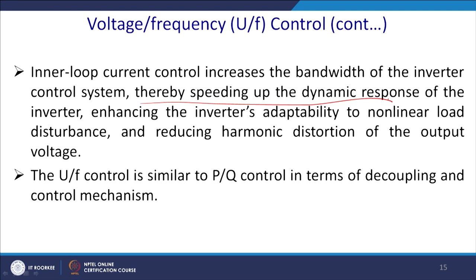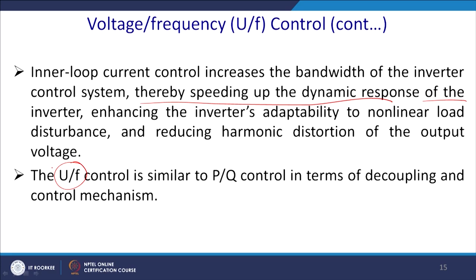The inner current loop increases the bandwidth of the inverter control system since the switching frequency is high — for example, if operating at 10 kHz, the bandwidth is 10 kHz while the supply frequency is 50 Hz, so it can act a thousand times faster. This enhances the inverter's capability to handle non-linear load disturbances and reduces harmonic distortion of the output voltage and other power quality issues. V/F control is similar to PQ control in terms of DQ decoupling, but V/F is applied for islanding mode while PQ control is applied for grid-connected mode.